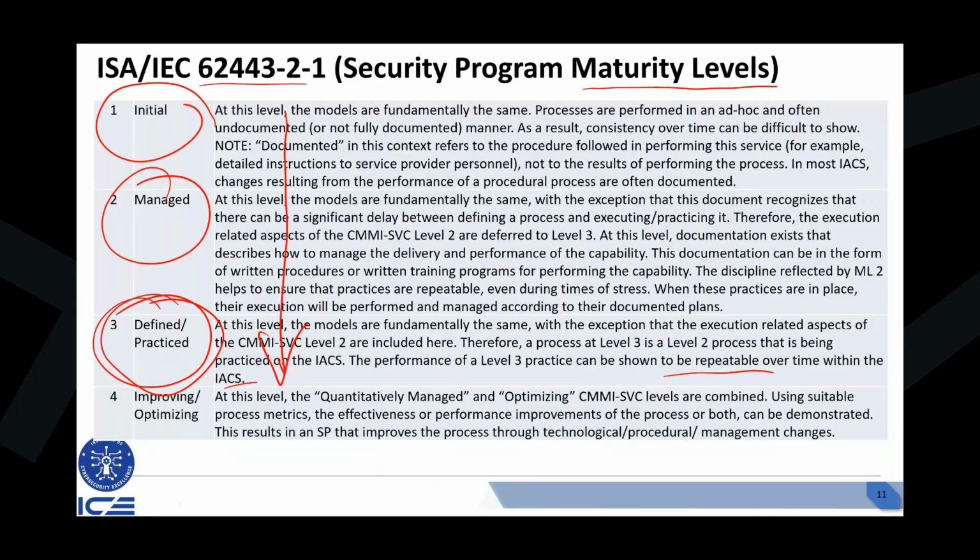I have seen in a power plant myself, they had disconnected the physical network cable, and they were saying, well, our system is isolated, period. It's impossible for anybody to get in. And I was like, okay, well, let me have a look at it. And guess what? We found that once a month, for 5 minutes, they bring in a portable Wi-Fi 3G adapter from the telecom provider, connected to a system, because they have to take the report for how much power was produced. They connected just for 5 minutes without any kind of controls, without any firewall, and they take the report and they say, okay, well, our system is secure.